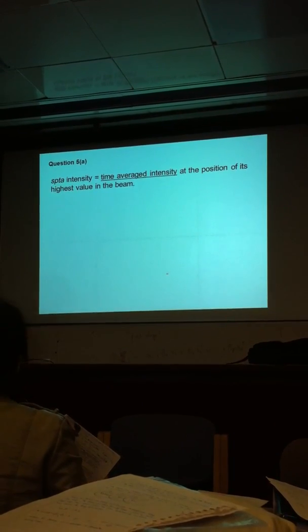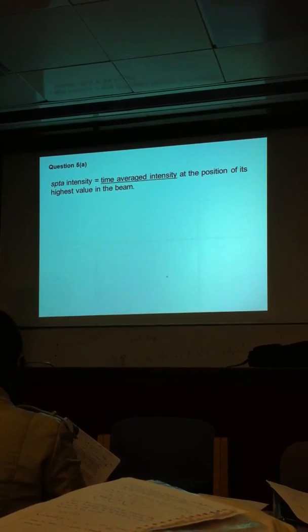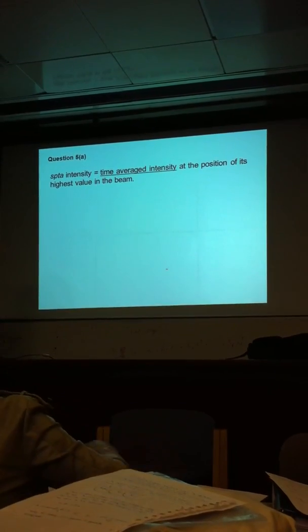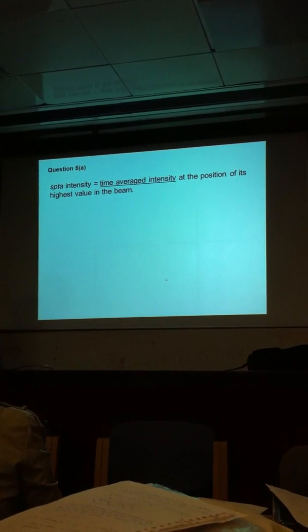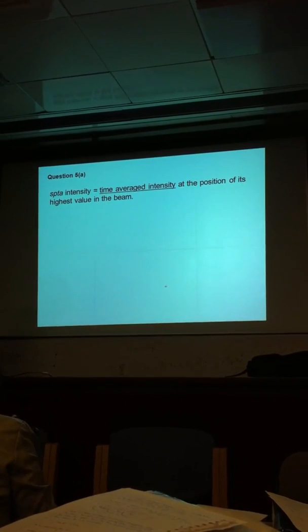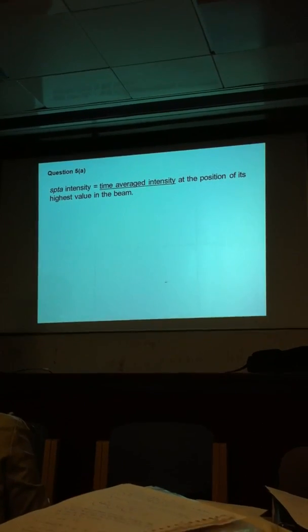Yeah? It says in the notes that it doesn't necessarily locate the beam axis to the focus. Well, that's where it's in a perfectly ideal system, particularly if you're talking about phased arrays. The actual pulse profile is a lot more complicated. They're not perfectly circular. It's going to be a challenge. And also, it depends on the tissue.